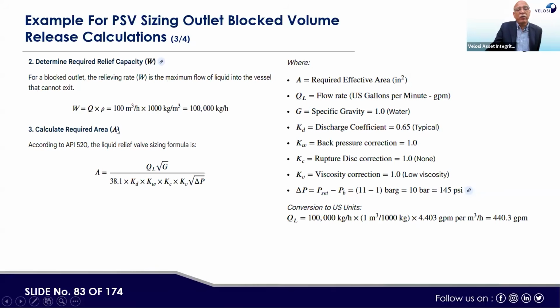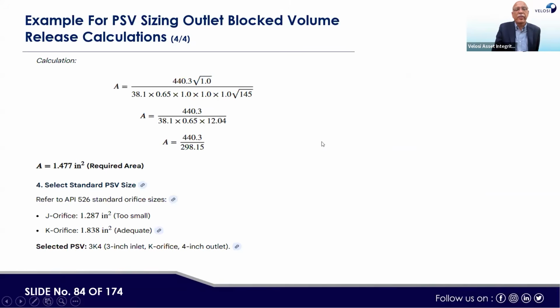Then determining the relief capacity, W is equal to Q into rho, the formula is applied. Then calculation of the required orifice area, this is the equation, and these are the variables, and dimensional consistency is required to be followed. Then after the normal conversion to US units, QL is equal to 440.3 GPM, so that all are in one unit system. Here the calculation is applied, and then we got the orifice area 1.477 square inch.